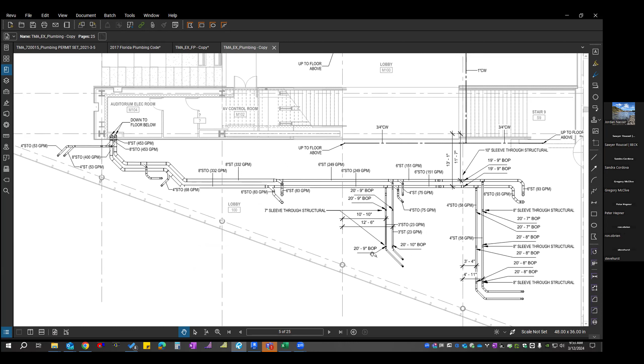I can flip through these overalls. They don't show a ton, since a lot is captured in the enlarged views. The overall shows a lot of the storm coordination, which was heavily coordinated because it's sloped pipe with insulation, coordinating around ductwork and structural elements. We show dimensions off grid lines, bottom of pipe, and sleeve sizes. This was all previously coordinated with structural, so it will need to be tightly followed during construction.